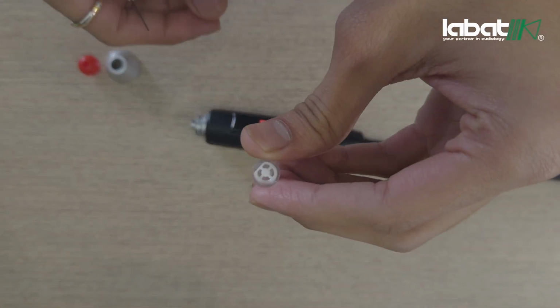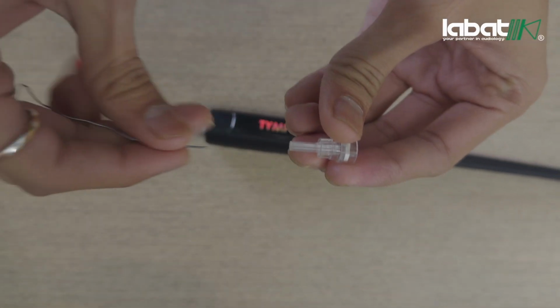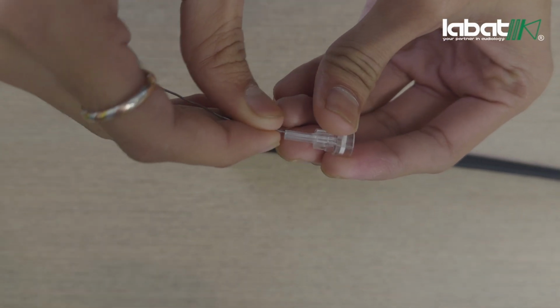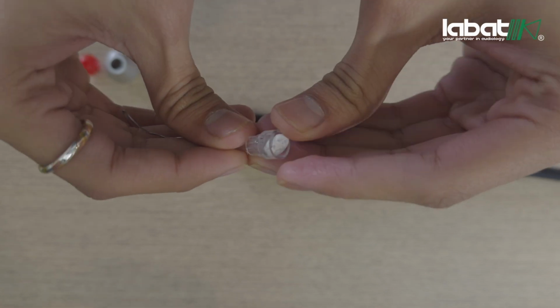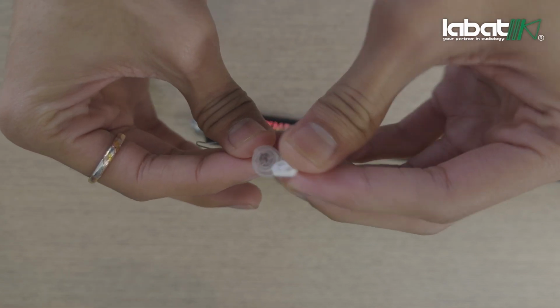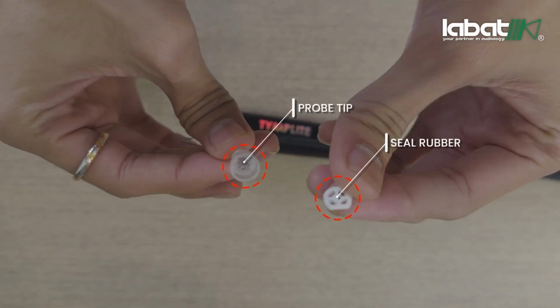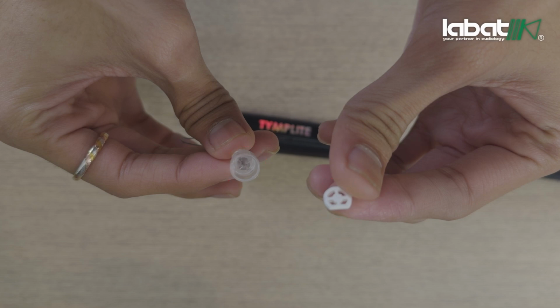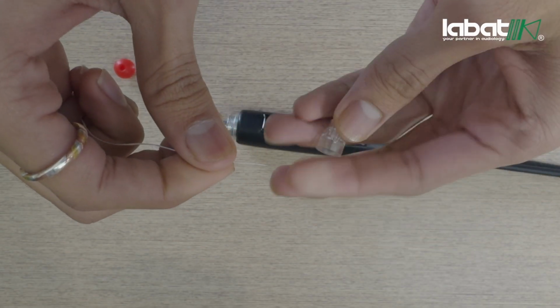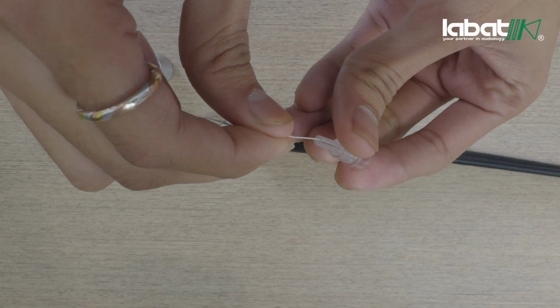To remove the seal rubber, use a suitable tweezer or a thin wire. Inspect the seal rubber and probe tip for wear and tear and presence of wax or dirt. If the seal rubber or probe are found to be damaged, replace them immediately. If wax or debris is observed, remove it carefully using a dental floss or a thin, soft tool such as a wire.